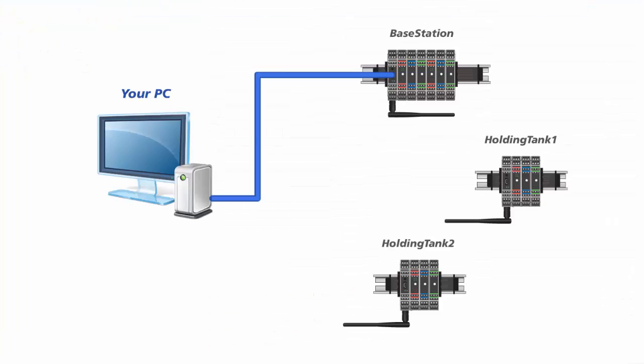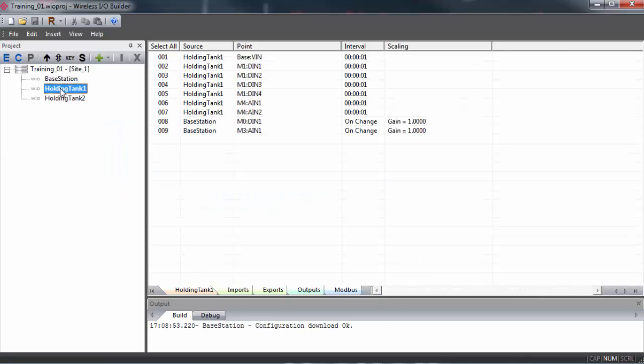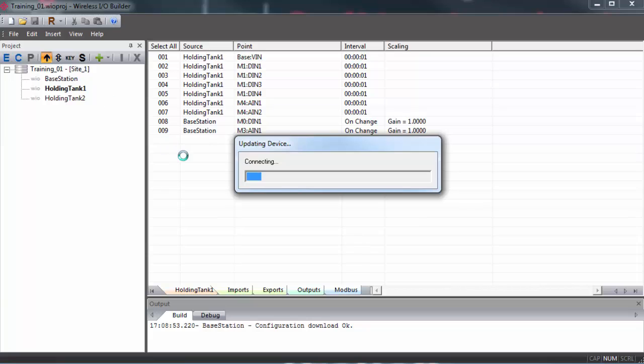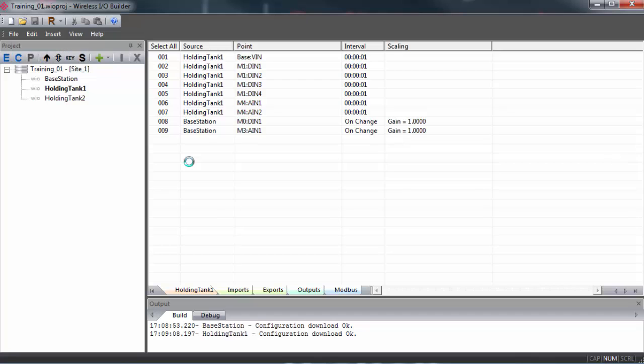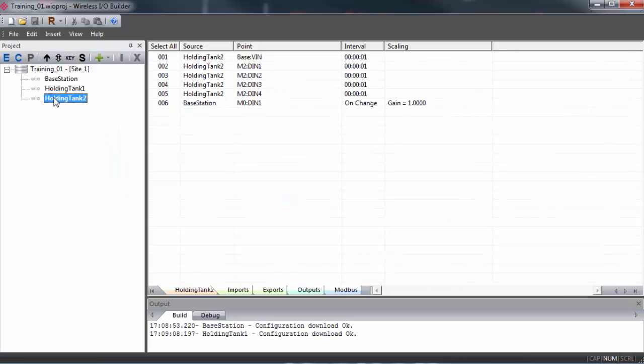And when this is done, we'll have to plug into each of the other gateways, making sure that they are selected in the tree view, and update them as well. Any time you make changes to the communication parameters or the mapping of points on a gateway, you're going to have to plug in and update the configuration.